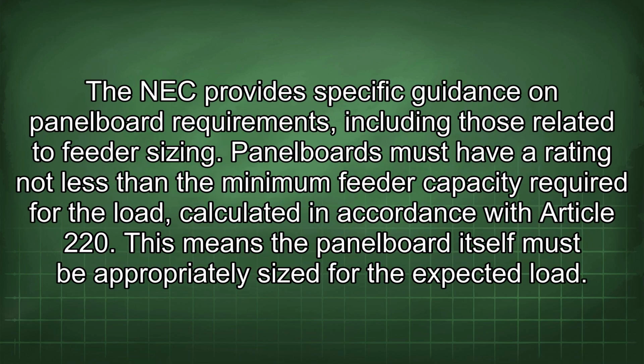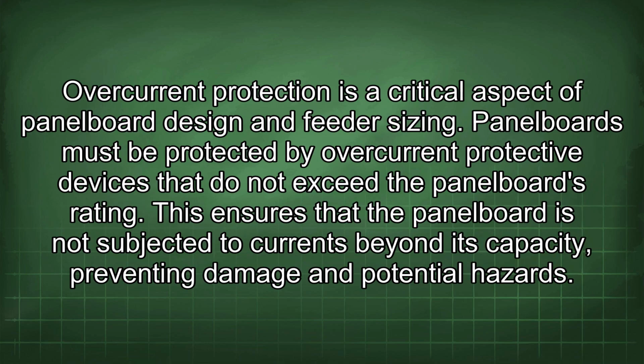The NEC provides specific guidance on panel board requirements, including those related to feeder sizing. Panel boards must have a rating not less than the minimum feeder capacity required for the load, calculated in accordance with Article 220. This means the panel board itself must be appropriately sized for the expected load. Overcurrent protection is a critical aspect of panel board design and feeder sizing. Panel boards must be protected by overcurrent protective devices that do not exceed the panel board's rating. This ensures that the panel board is not subjected to currents beyond its capacity, preventing damage and potential hazards.